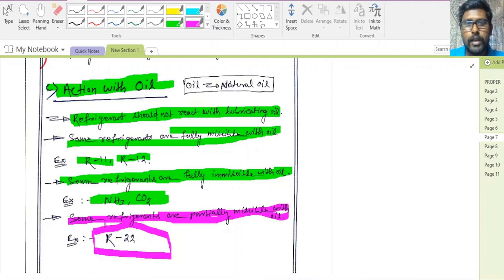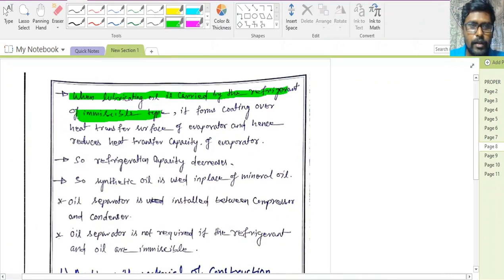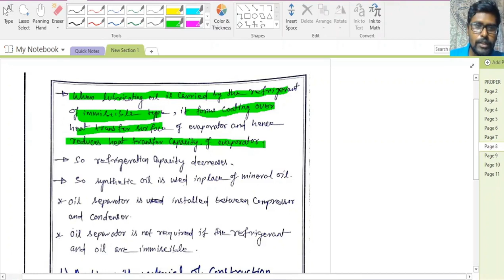When lubricating oil is carried by a refrigerant of immiscible type, it forms a coating over the heat transfer surface. When it flows through the condenser or evaporator, it forms a coating on the condenser pipe surface or evaporator pipe surface, and hence it reduces the heat transfer capacity of the evaporator. So refrigeration capacity decreases. The oil will decrease the heat transfer coefficient, so the heat transfer inside the evaporator will decrease, and it will decrease the capacity of the refrigerator.